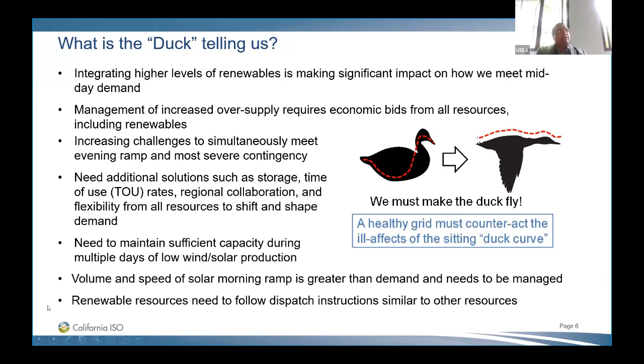This last bullet is really important: we need renewable resources, any kind of inverter-based resources—wind, solar, storage—to be able to follow dispatch instructions from the system operators. Sometimes people think being able to move fast is good, but sometimes it's not. Currently we're looking at ways to slow the response, especially from solar. Solar can move very fast, it can move in cycles, but remember you've got conventional units in any fleet, and you have to judiciously balance that supply and demand.